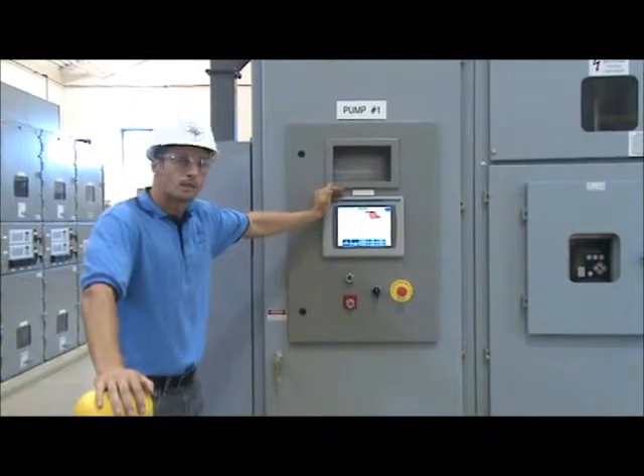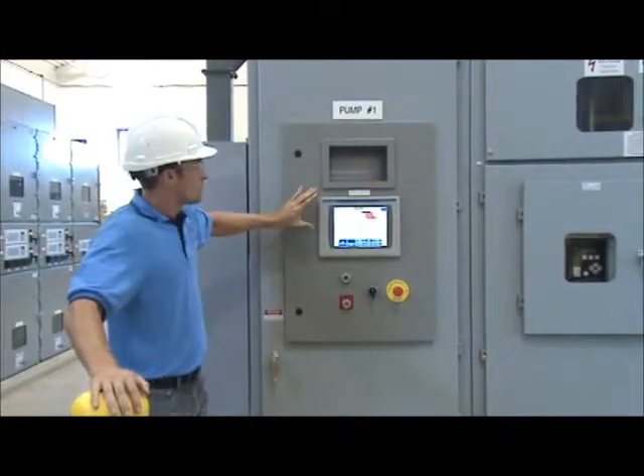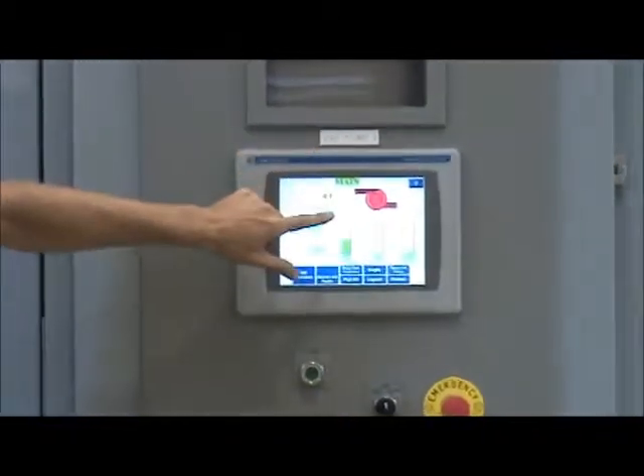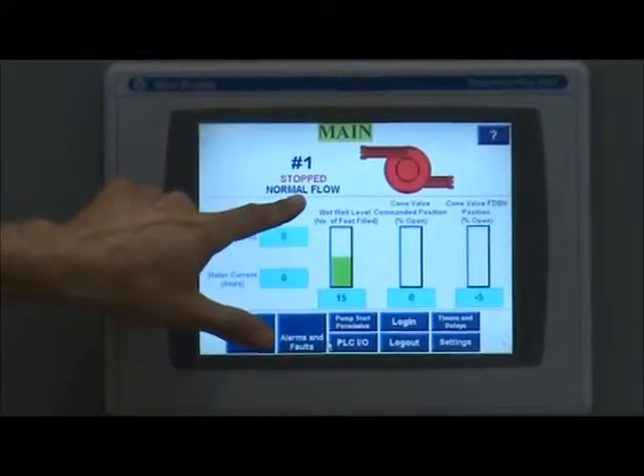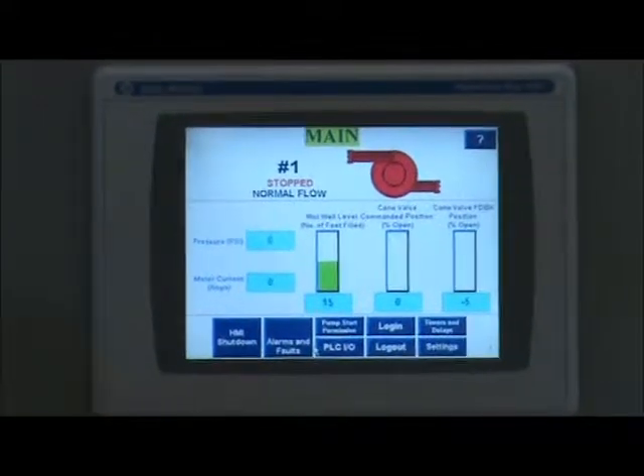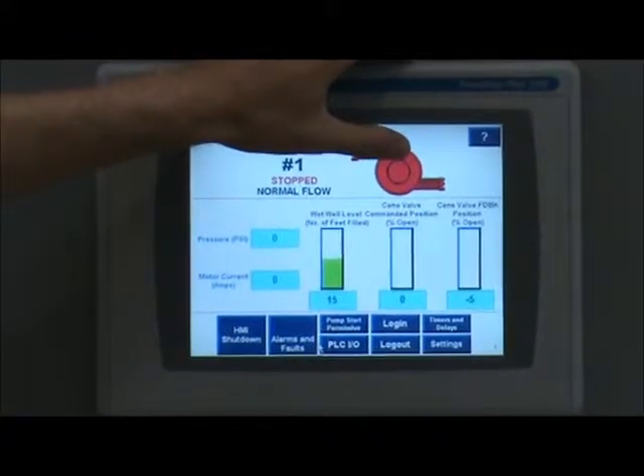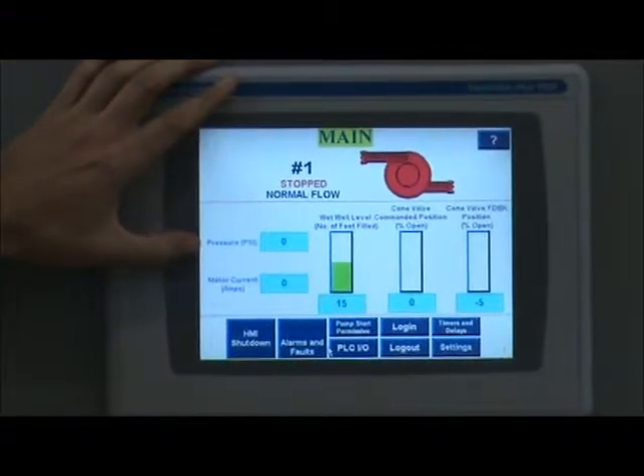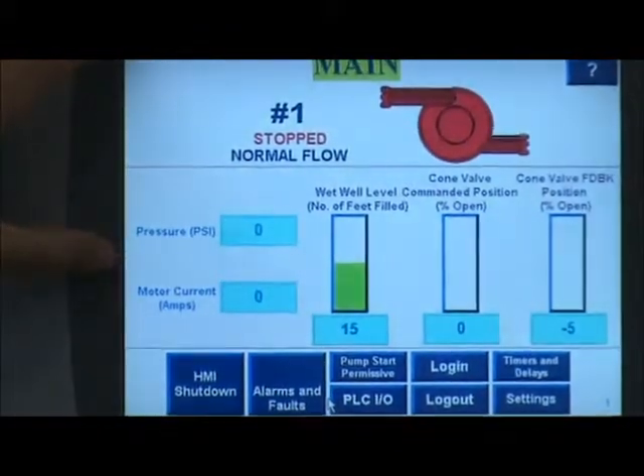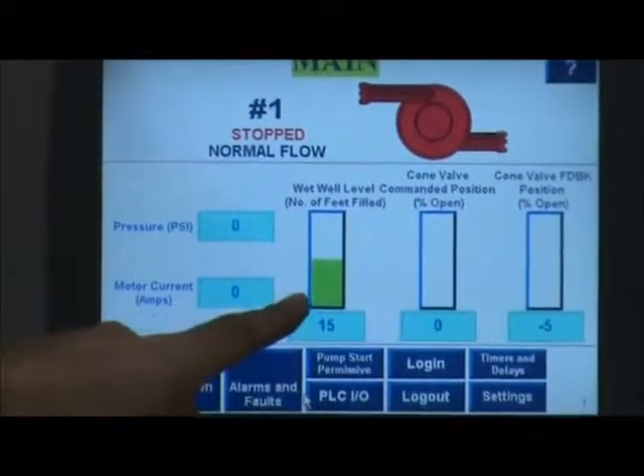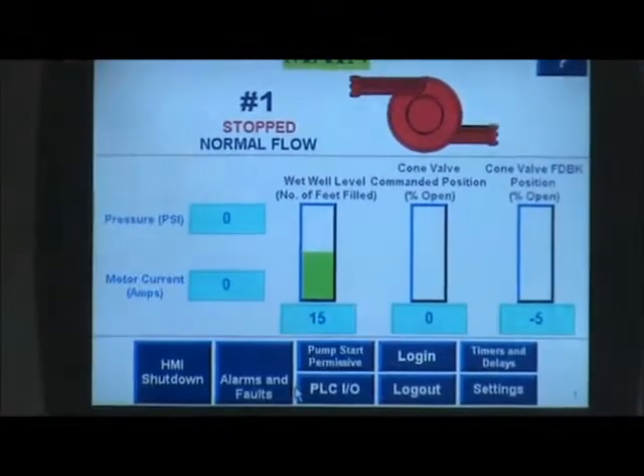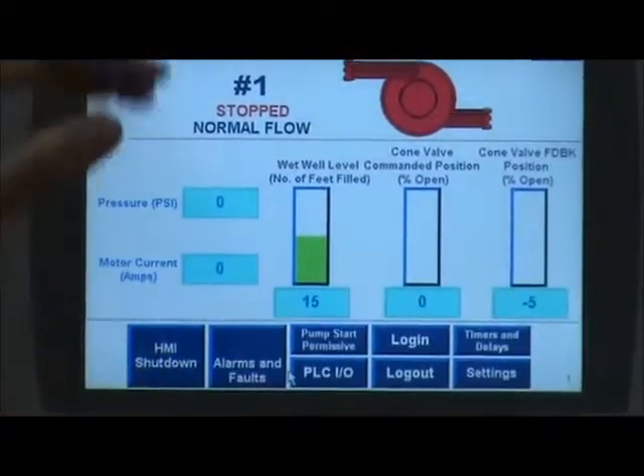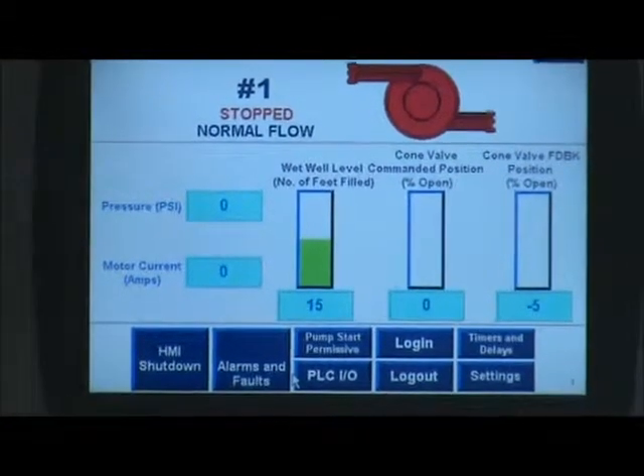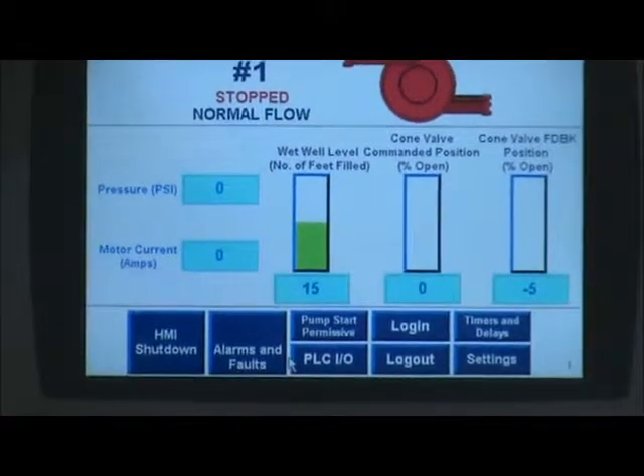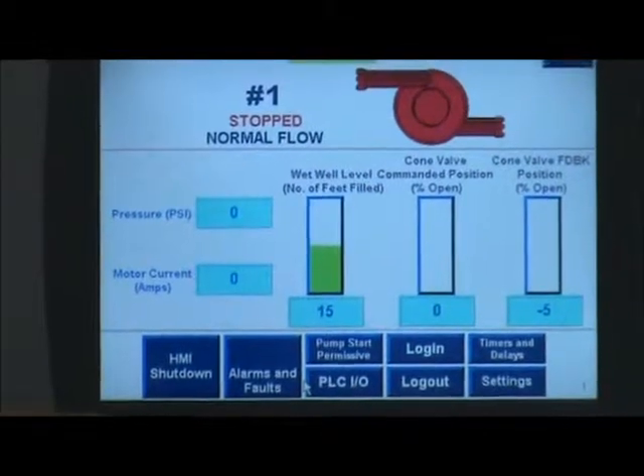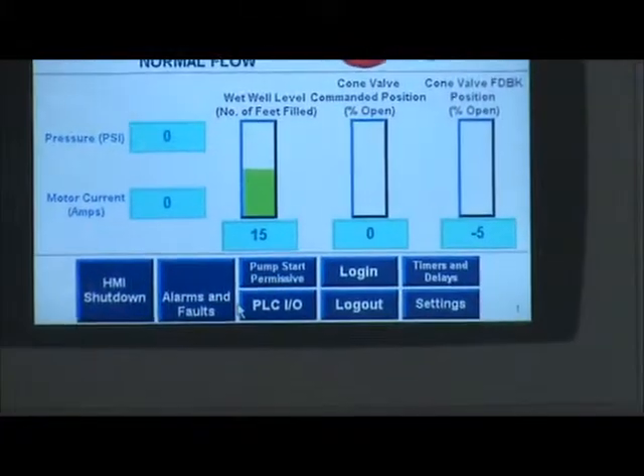This is the Allen-Bradley PanelView 1000 that we chose as our HMI. This is the main screen, which shows your current pump operation and your pump selected flow rate, and then you have a visual cue of the pump being red for off, green for being run. You show your downstream pressure from the transducer, our motor current. We have a display for our wet well level, for our commanded position for the cone valve, and then the actual feedback position of the cone valve. And then there is a help screen that tells you all the visual cues of what you're looking at. And then here at the bottom are buttons to navigate through the other screens.